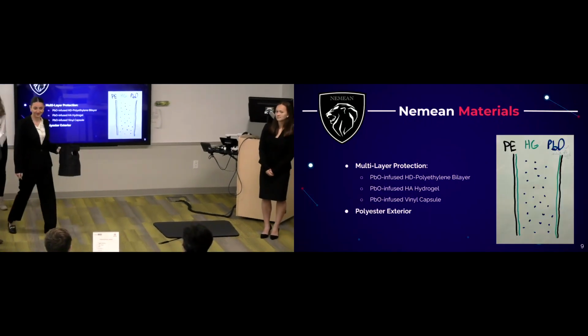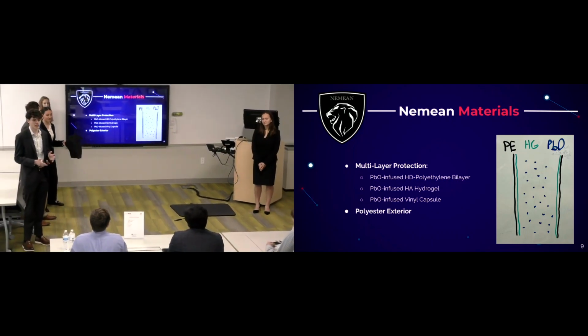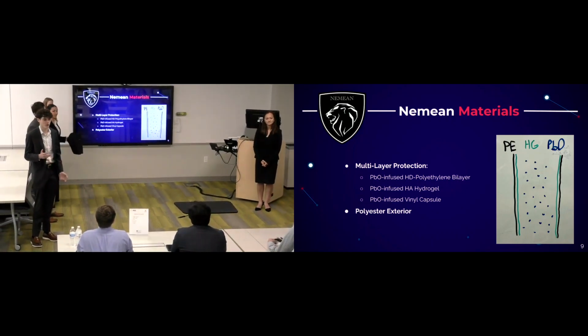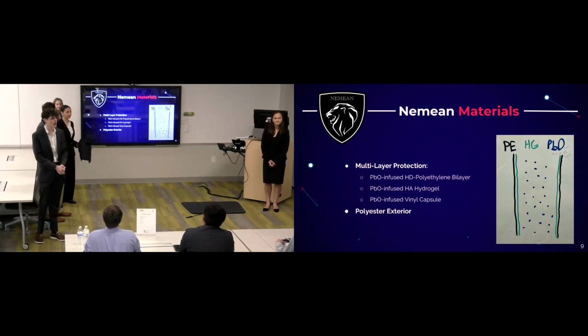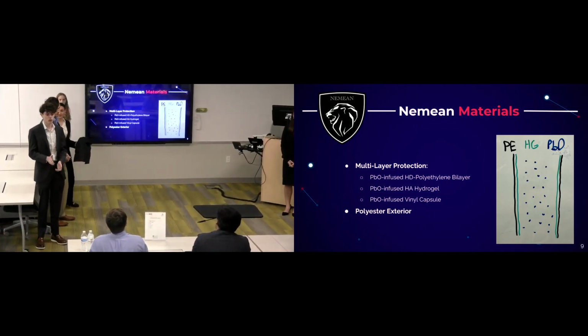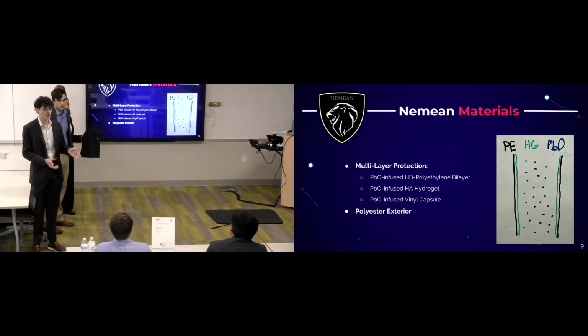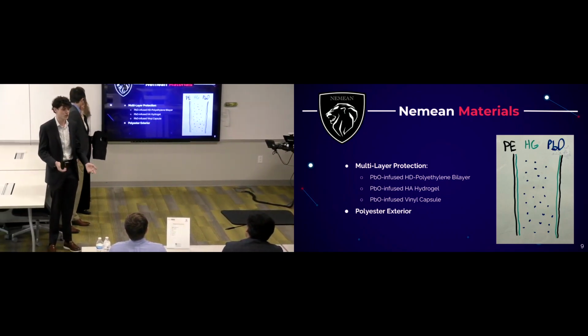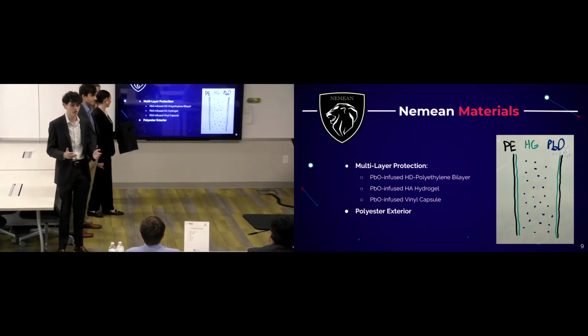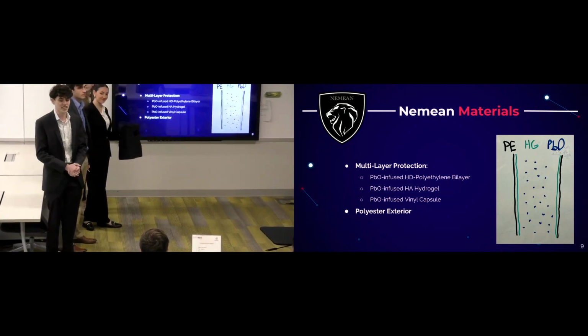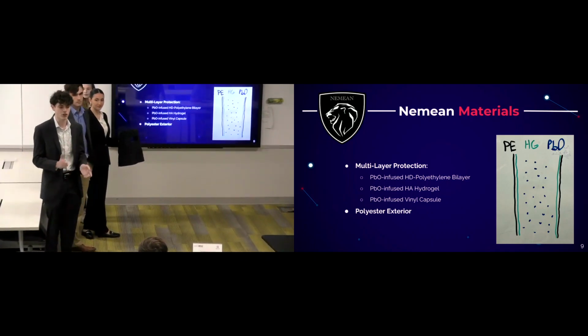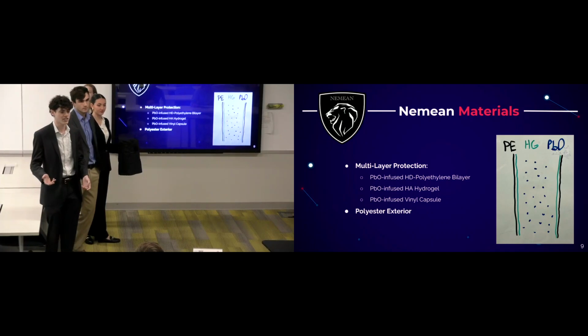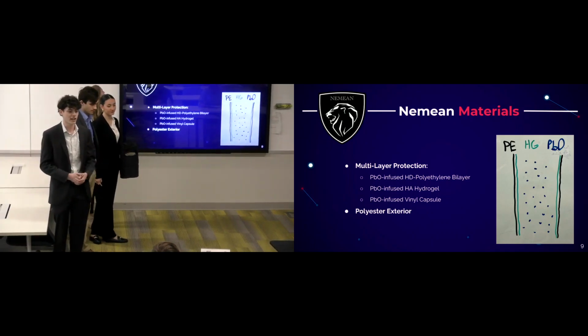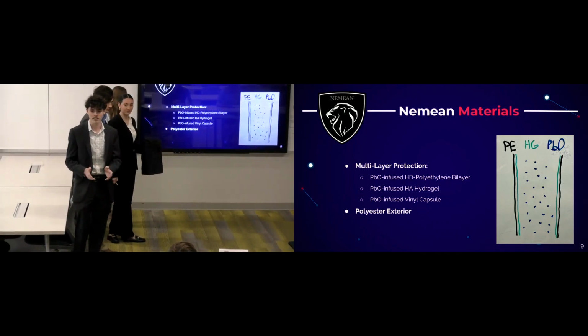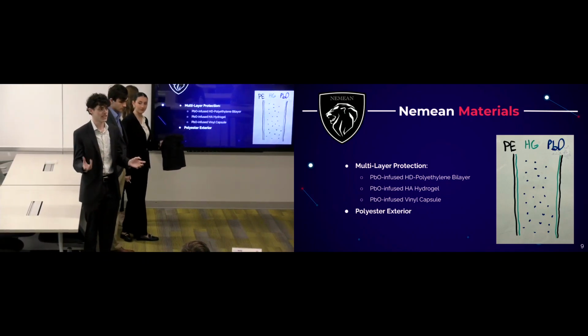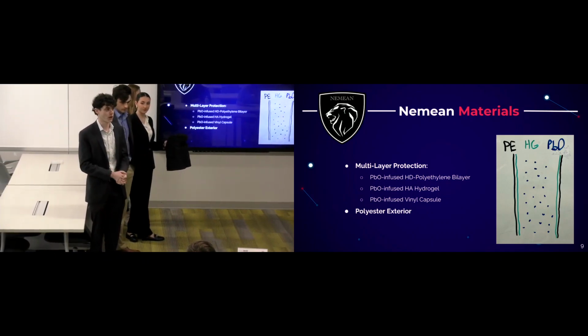So the materials for the Nemean, after extensive research on affordable and lightweight materials that are known to have radiation shielding properties, we've identified a few. Each one of these materials we've decided to infuse with lead oxide, which is an industry standard for leaded glass to prevent radiation from getting to individuals. It's typically done in ranges of 20 to 30% by weight in this glass. So for each of these layers, we decided on a 30% lead oxide by weight to prevent radiation from getting to our physicians.